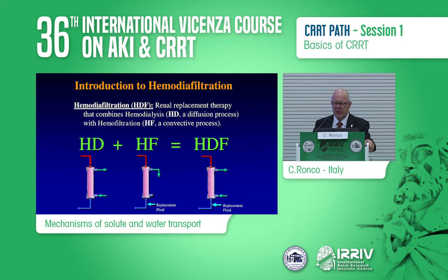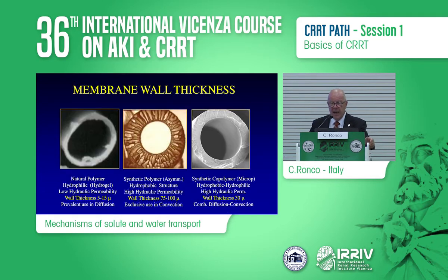Hemodiafiltration is a combination of hemodialysis and hemofiltration, combining well diffusion and convection. In the past, we used to have low flux membranes that were characterized by a very thin membrane optimized for diffusion. We had thick, hydrophobic membranes optimized for convection. And recently, we have membranes with a hydrophobic, hydrophilic configuration with reduced wall thickness, and finally, they can be combined in diffusion and convection.